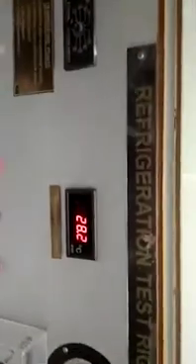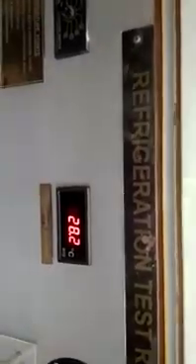You see the temperature knobs. We have 5 temperatures. T1 gives the compressor inlet temperature, T2 the compressor outlet temperature, T3 the condenser outlet temperature, T4 the temperature after the expansion process, and T5 the freezer temperature. You can see the knob. By pressing T1, you can change to T1. You see 28.1 degrees Celsius is T1, the compressor inlet temperature.